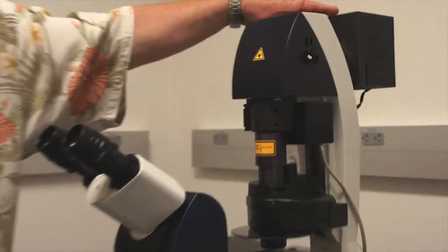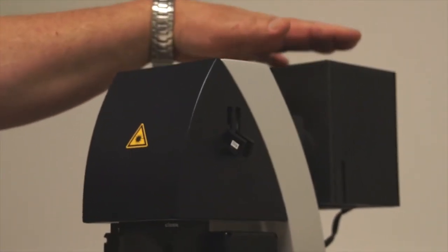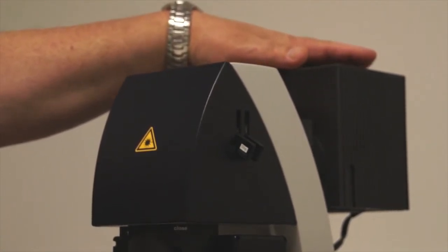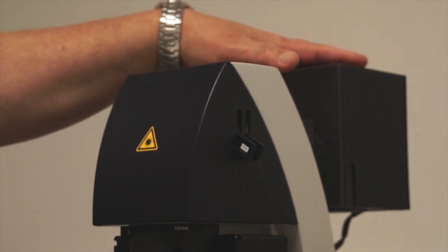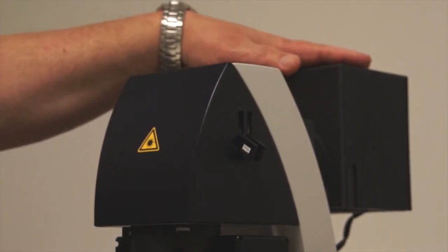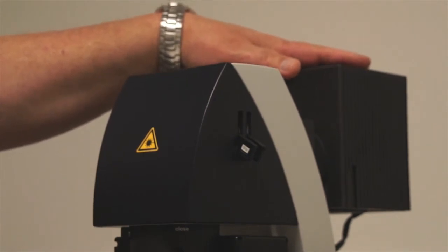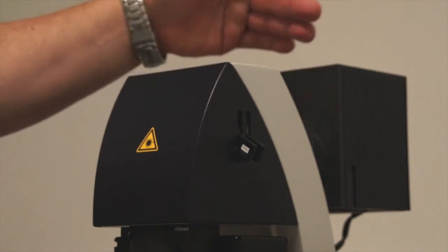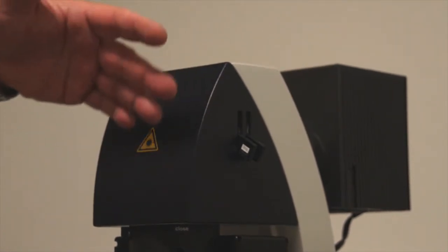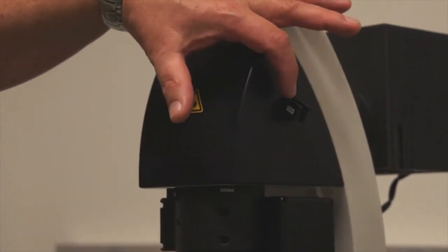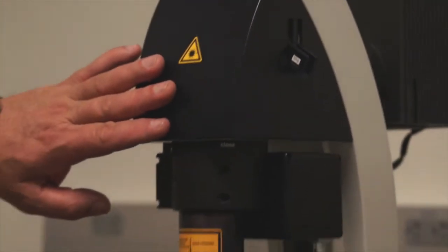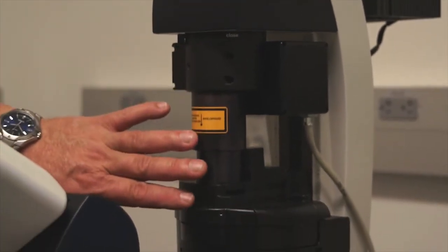The transmitted light illuminator has a lamp house back here, and this is where the halogen 100-watt bulb is. When you turn on the microscope, this bulb is on all the time. And so in a few minutes I will show you the intensity control switch to turn down this bulb so that it's not burning all the time. The light comes out of the lamp housing and it goes into a collector system. There are two flip switches here, but those you don't need to play around with. We'll discuss those later. The light comes through this device and comes down into the condenser.